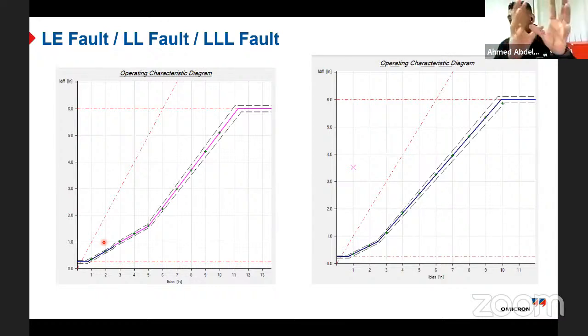Now I have an ABB relay as the main one, because in a substation we usually have main one and main two. So I have an ABB relay and I have a Siemens relay. If I put these two relays together to protect the same transformer, am I sure this will work together or not? Here, we need to think about something different, something more reliable. We call it system-based testing.